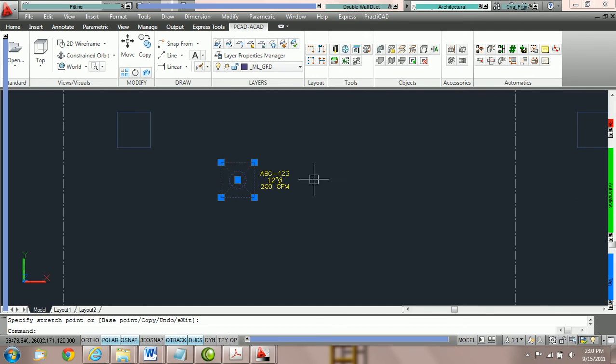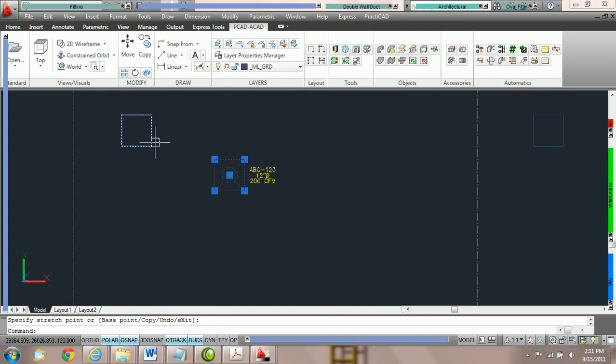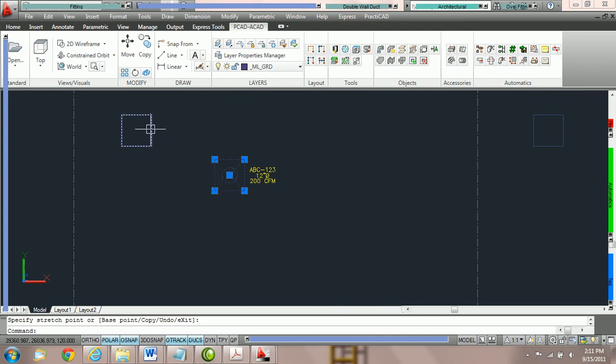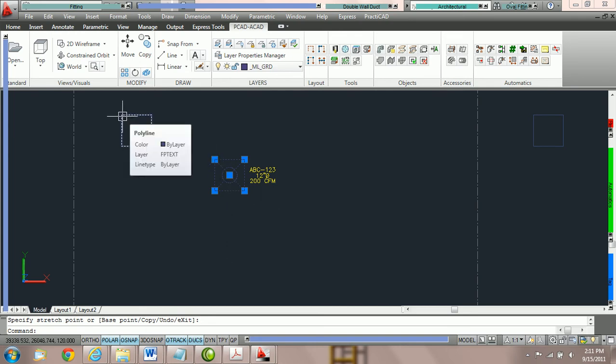But one thing we must be very careful to do is we are going to take this grill, and we're going to snap it to the background that was given to us by the engineer. And this background happens to have an elevation of zero, zero. You'll notice if you click on your grill that the elevation should be at bottom 10 foot. So if we don't use our replace Z option, and there's tutorials on replace Z, we're going to move and snap this to the background. And it's going to negate the elevation of 10 foot we have.